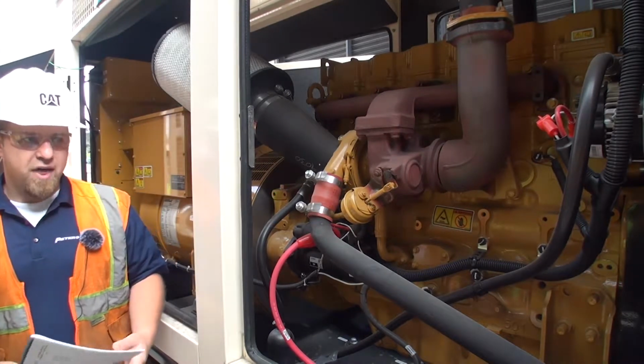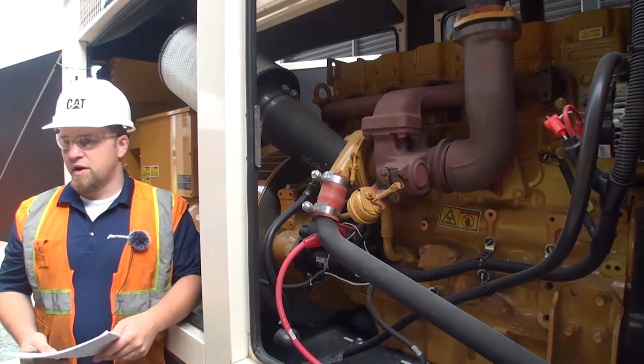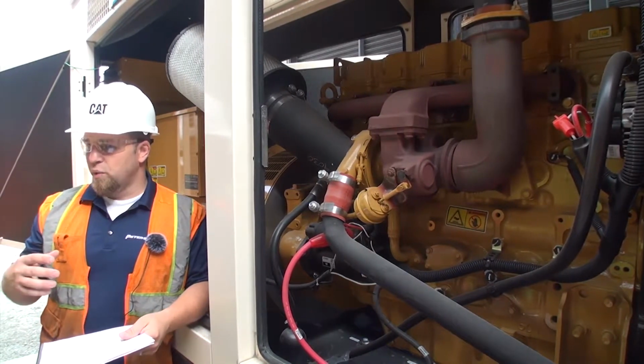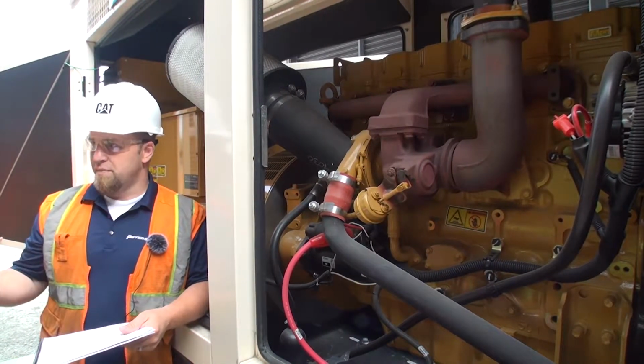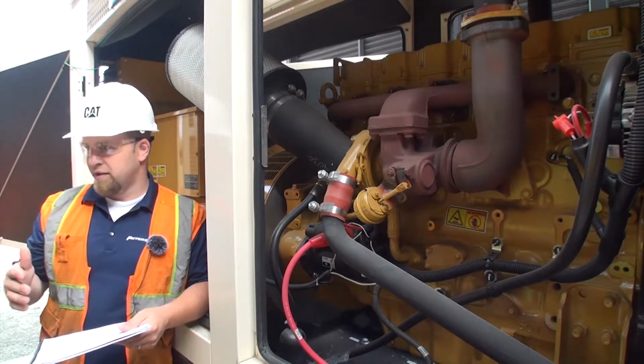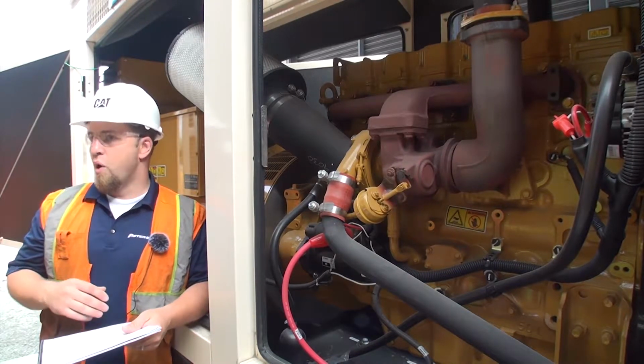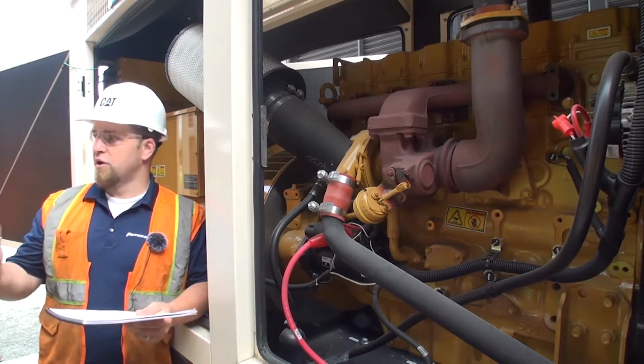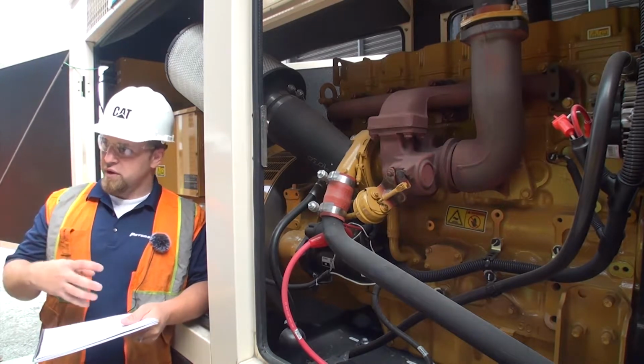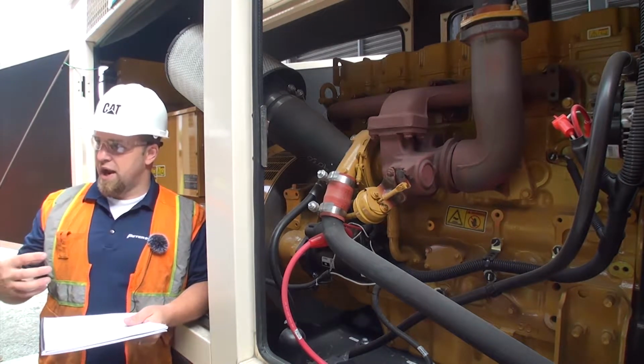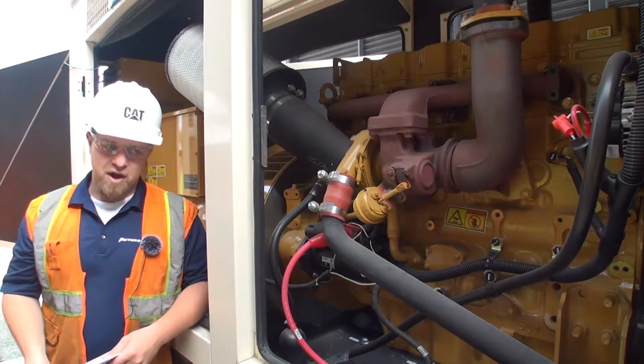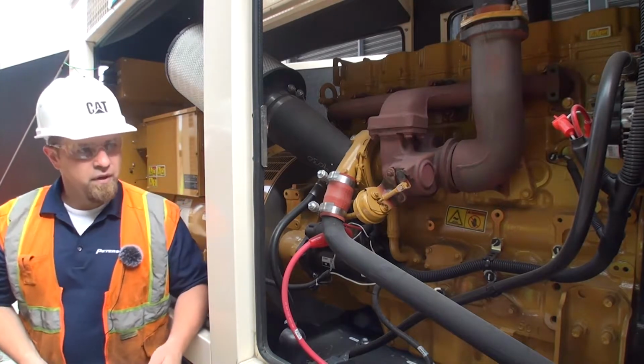So watch for that. If it starts happening, think about either doing less time on your weekly run, moving from a 10 or 15-minute run down to 5 or 10 minutes, or doing your building transfer for a longer period so it's under load longer to try and burn that out. Just something to think about, especially on the older units, you'll see it.